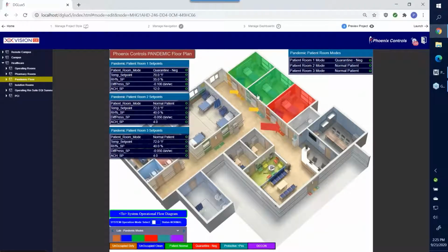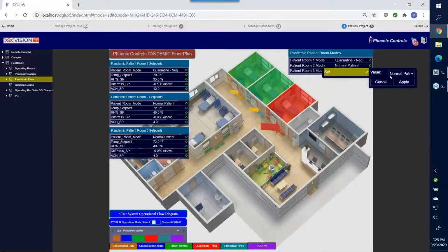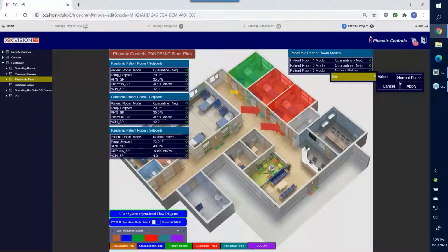Now, I'm going to point out, just as we're going through this, that immediately patient room 1 went not only negative, but the set point changed to 70 degrees. It could be whatever you want it to be. The differential pressure set point is now negative 0.1, and the air change rate is now at 12, as opposed to these, which you see down here, which haven't been changed yet, where we're at 0.05, 72, and 4. So you'll see these independently and immediately changing, again making it a very simple mode where all the person has to do is say, I want to change this from one mode to the next. And you'll see the ability to change not only the rooms, but also the associated air handling unit, to change this into a completely pandemic floor in a matter of seconds.